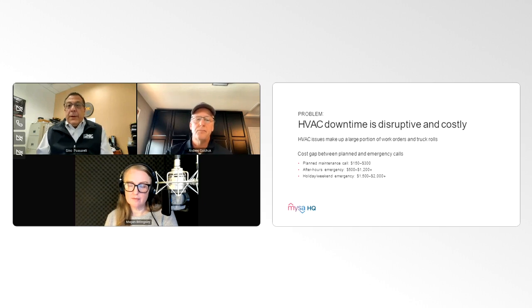Yeah, and I could agree with that. And to add to that, especially the history of what is being done on each individual unit is extremely important. When you look at ASHRAE standards, which is the industry standard, the typical life of a simple rooftop is approximately 15 years. And what we found through proper maintenance and doing the things that manufacturers expect to be done on their equipment throughout that lifespan, you could very easily get 20, 25, and in some cases 30 years out of that life of the equipment.